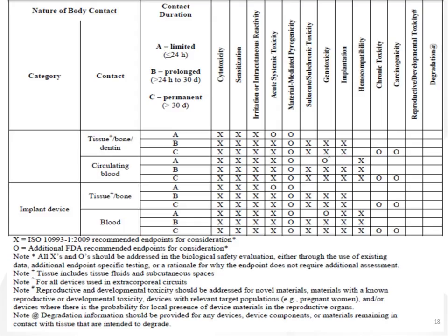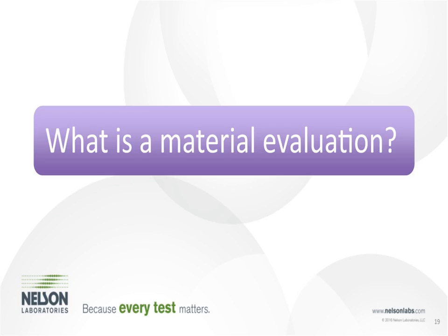We're not asking you to test packaging materials separately, but you need, once again, to evaluate the risk of that packaging to your device. Does it transfer? Is there melt? We've seen plastics melt onto a device or transfer inks from a label. These kind of things need to be evaluated. And it may be that your testing may have to be packaged in its final configuration through all its processing to evaluate any potential transfer. But those things should be spelled out in your biological evaluation plan.